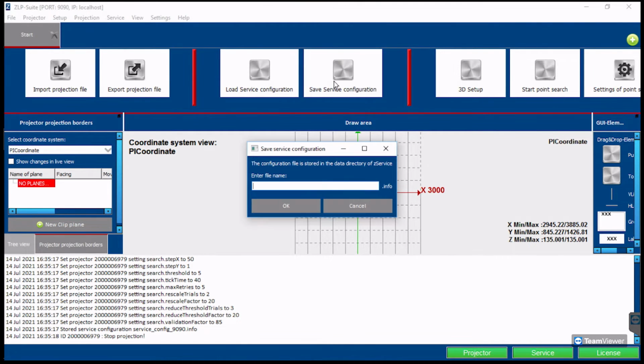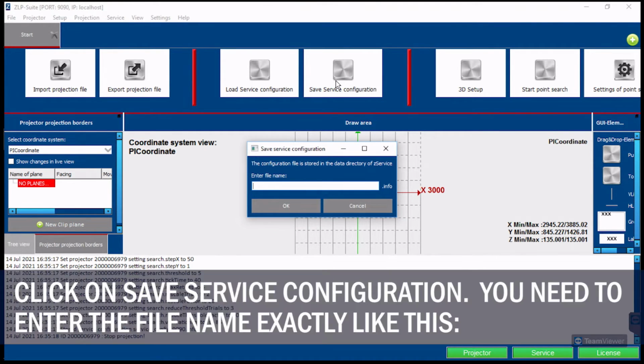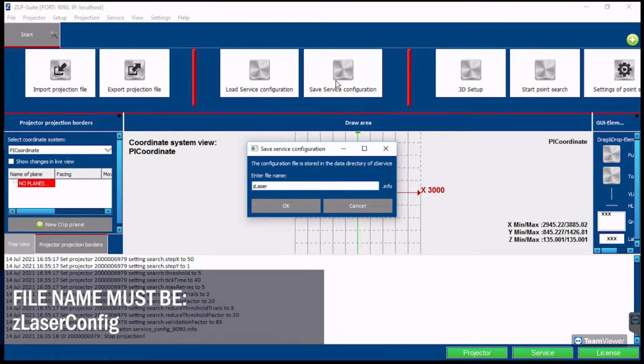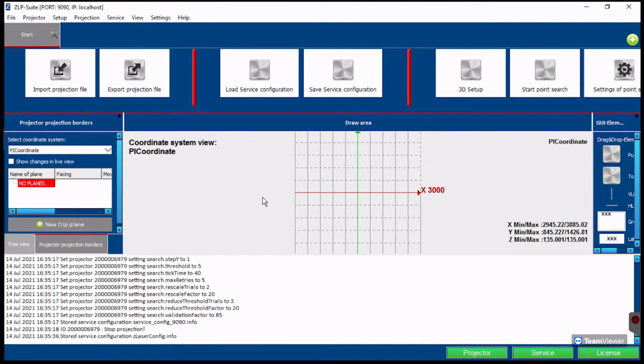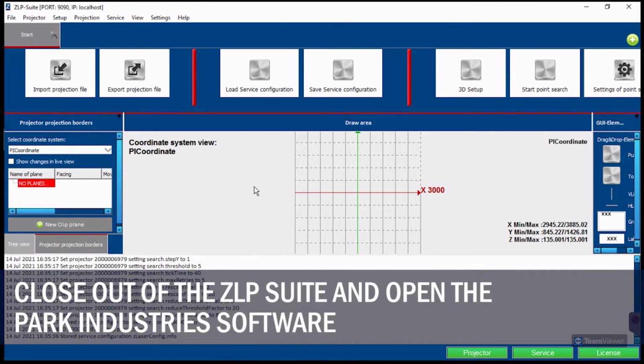Next, we need to save our new calibration. Click on Save Service Configuration, and make sure you enter the file name as shown, zLaserConfig. It needs to be lowercase z, capital L, capital C, for the laser to communicate with the front end. If you save it differently, it will not work in the Titan software.